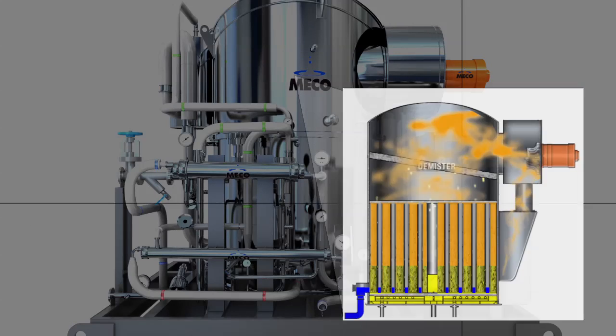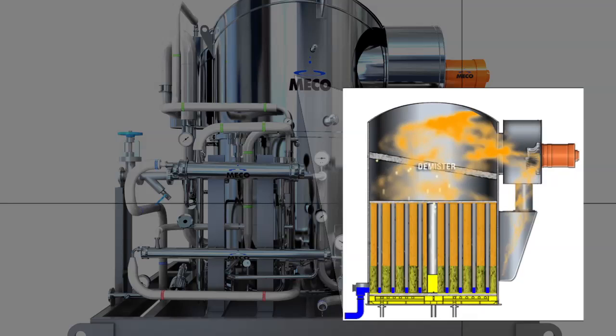A demister removes entrained water droplets from the vapor which is withdrawn by the compressor. When the vapor is discharged in the evaporator on the outside of the tube bank, it gives up most of its latent heat to feed water inside the tubes. More vapor is generated and the process continues.